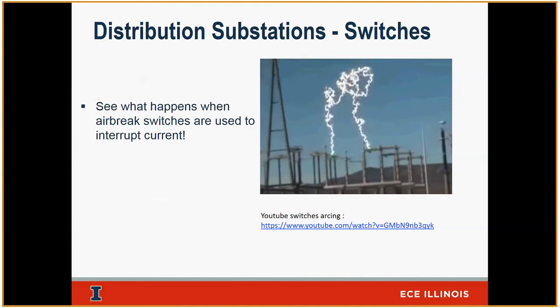The next component of the substation we'll talk about is a circuit breaker. That's what we would use. Circuit breaker would de-energize the entire line, and I'll go a little bit more into operations. So in the real world, you'll have a guy standing here waiting by the switch. And then you get somebody sitting in a command center, push a button and de-energize the 69 kV line from its source. So from the main 69 kV source, this whole thing will become de-energized.